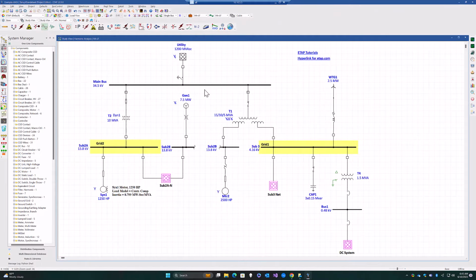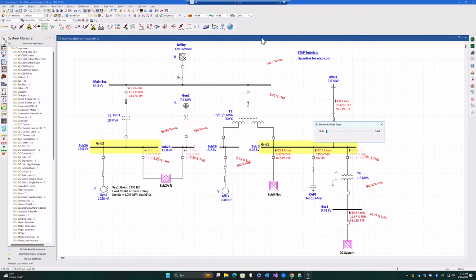For this demonstration, I'm using the example ANSI file that comes along with ETAP. So later on, if you'd like to play along and test drive these yourself, you can use exactly the same file without any other modifications. The balanced harmonic is available as a mode within ETAP, so you can run the harmonic load flow, and we report the RMS voltages, the voltage total harmonic distortion, the current harmonic distortion, as well as the total power factor, displacement power factor, and so on and so forth.